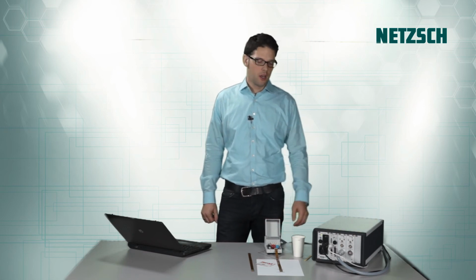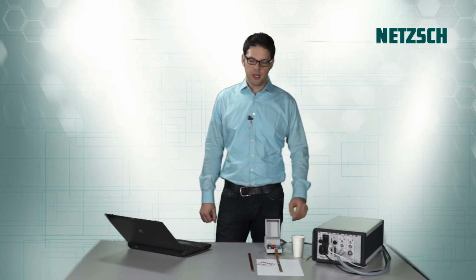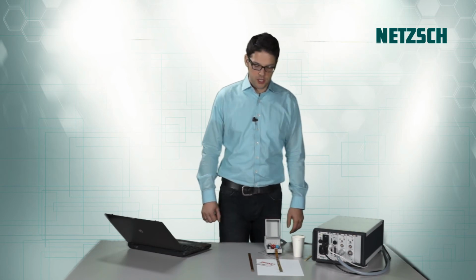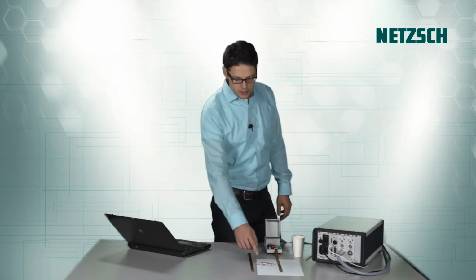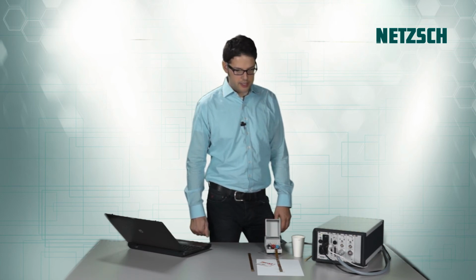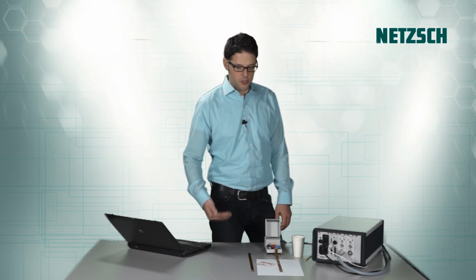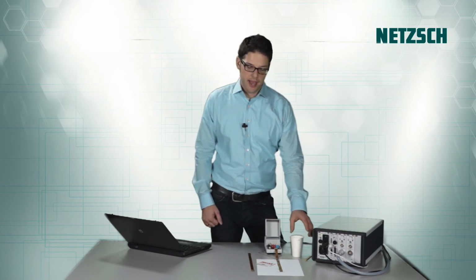In the next step, I would like to show you how easy it is to perform a measurement with a DEA 288 Epsilon. The material selected for this demonstration is a 2-component epoxy resin, which is inside of this small bag here. These bags are shipped with any instrument from Netzsch so that customers have several samples readily available to perform a measurement during installation to see if the system is working correctly. What I will do now is open the bag, mix the 2 components inside of this cup and apply the resin onto the sensor.